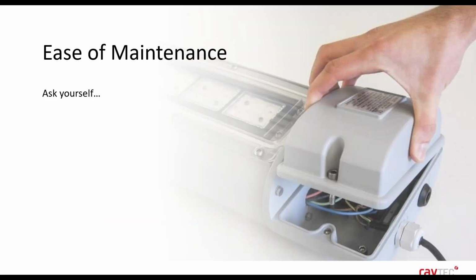One of the benefits of an LED luminaire is that it reduces the amount of maintenance interventions which are required, but even still, you shouldn't consider an LED luminaire as being maintenance free, especially if it's installed in a hazardous area. The nature of a hazardous area means that there will always be some routine maintenance required, and it should be an important consideration for any electrical product, but especially when the luminaire is being installed in extreme environments like hazardous areas. Access is also often difficult, so maintenance becomes even more of an important consideration.